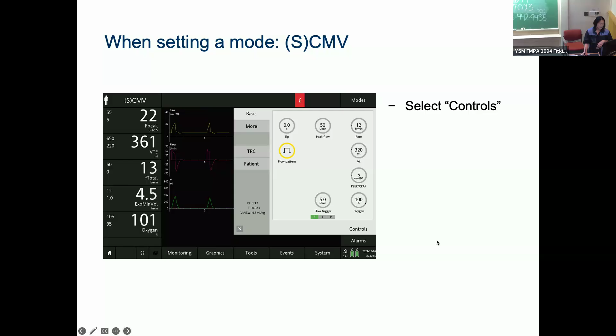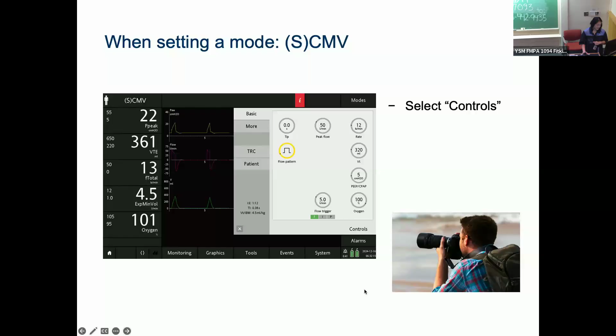It was not changeable. But on this ventilator, we can have all 3 options. We can have that deceleration to the 25, 30%. We can have a pure deceleration down to 0, or we can have this square waveform. I would say that if you could tell your residents that if they want to take a picture of the ventilator so they could put the order in the chart, this is the picture to get because this has all the information. Whereas on the Avea, you used to take a picture of the home screen. Not so much anymore. So, all right.